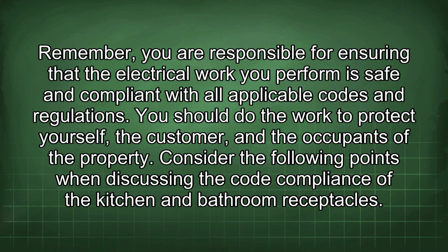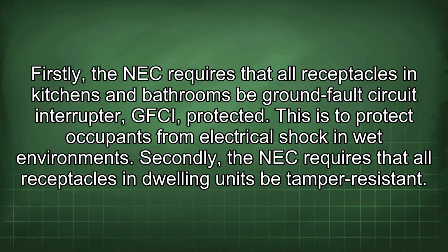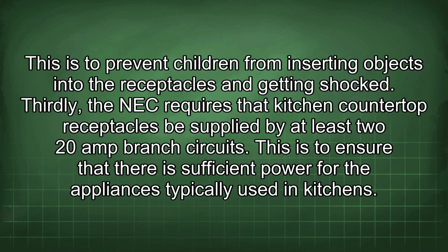Consider the following points when discussing the code compliance of the kitchen and bathroom receptacles. Firstly, the NEC requires that all receptacles in kitchens and bathrooms be ground fault circuit interrupter (GFCI) protected. This is to protect occupants from electrical shock in wet environments. Secondly, the NEC requires that all receptacles in dwelling units be tamper-resistant. This is to prevent children from inserting objects into the receptacles and getting shocked. Thirdly, the NEC requires that kitchen countertop receptacles be supplied by at least two 20-amp branch circuits. This is to ensure that there is sufficient power for the appliances typically used in kitchens.